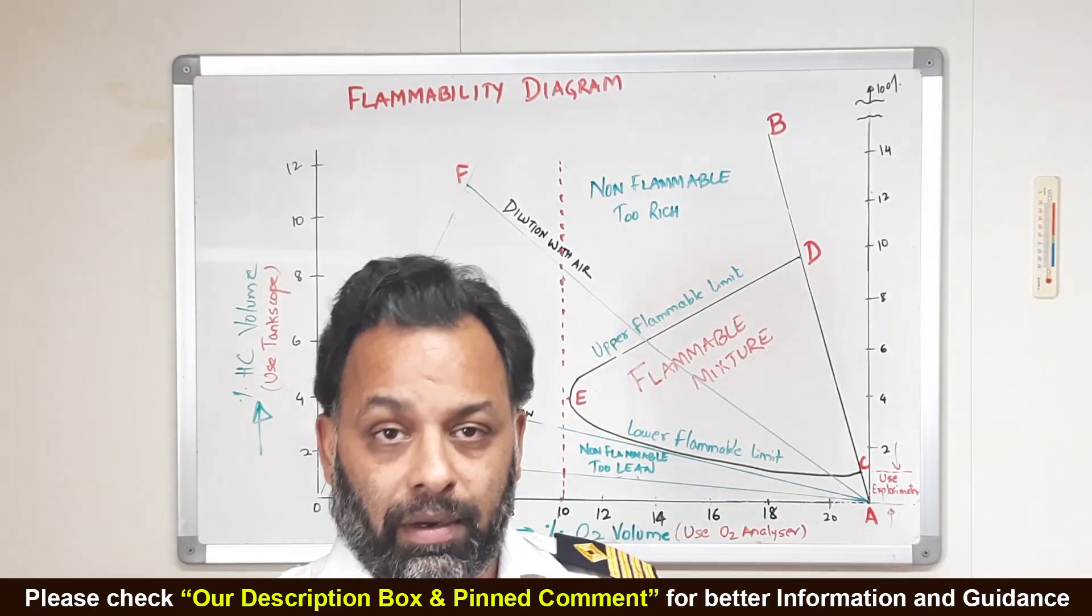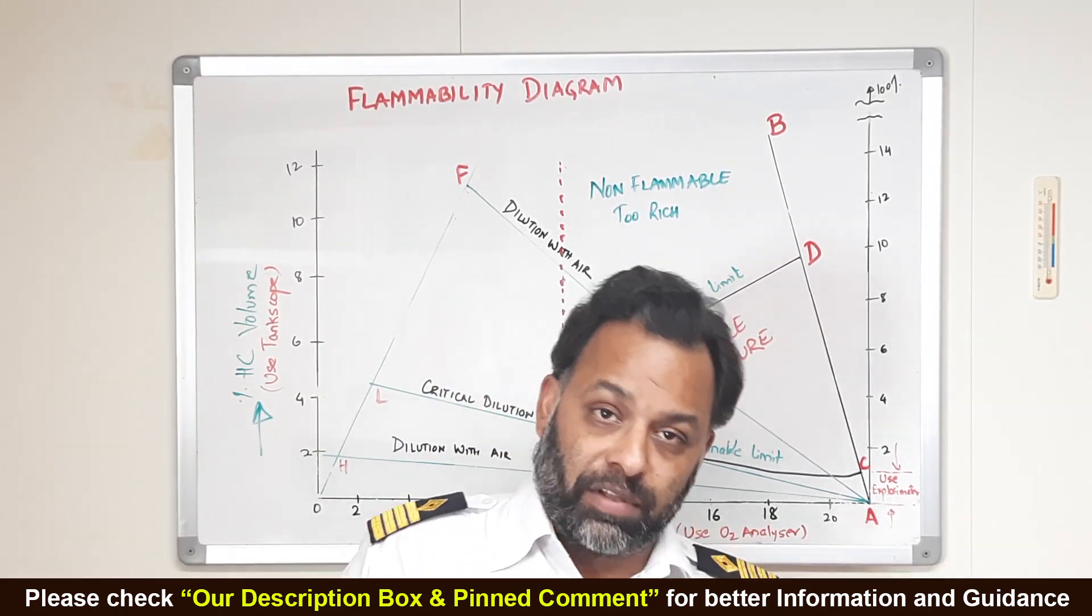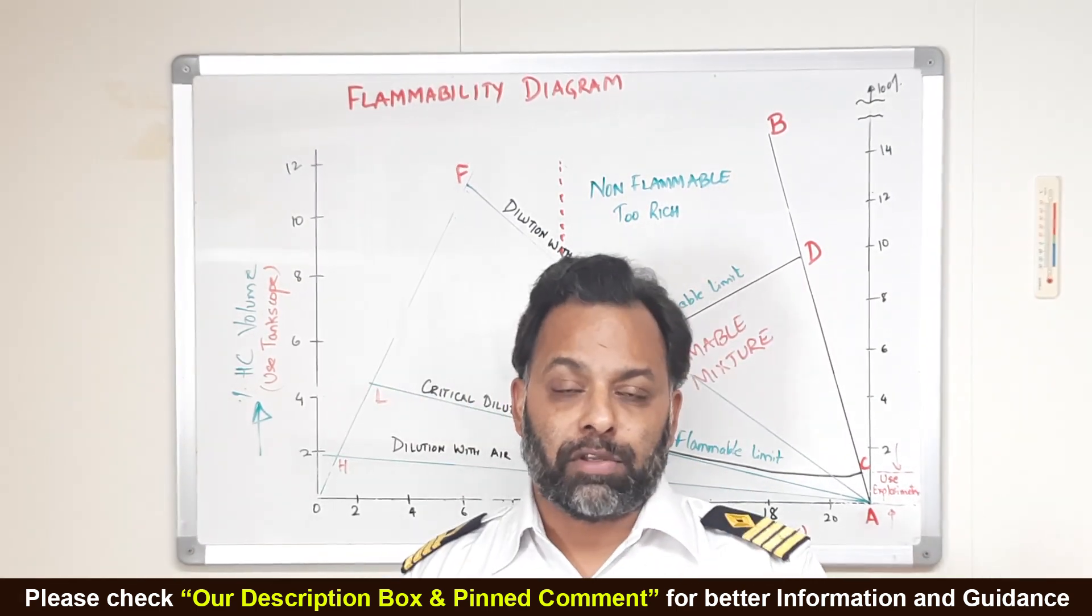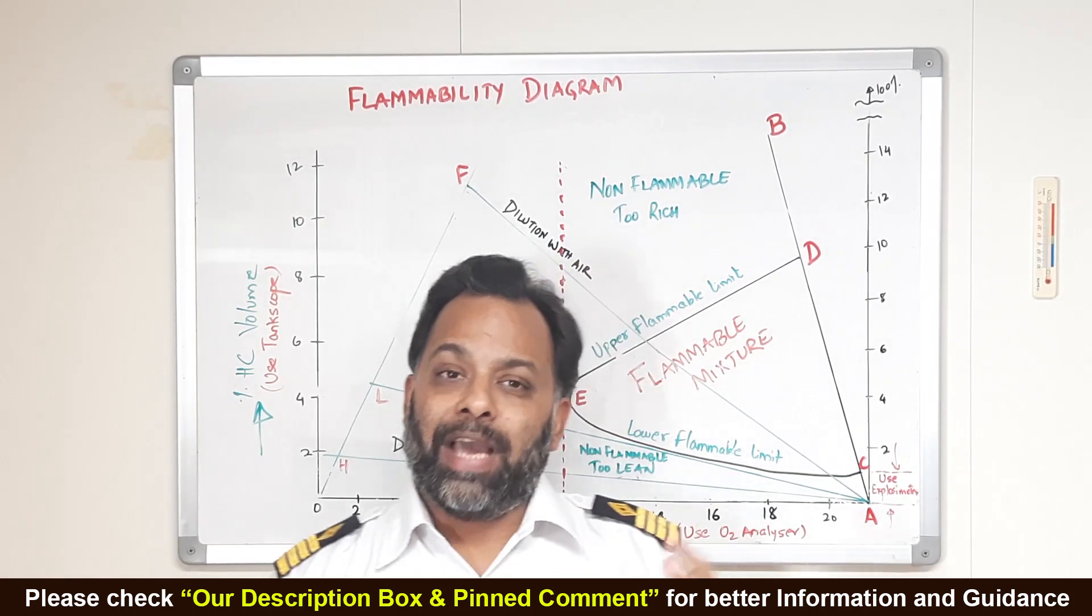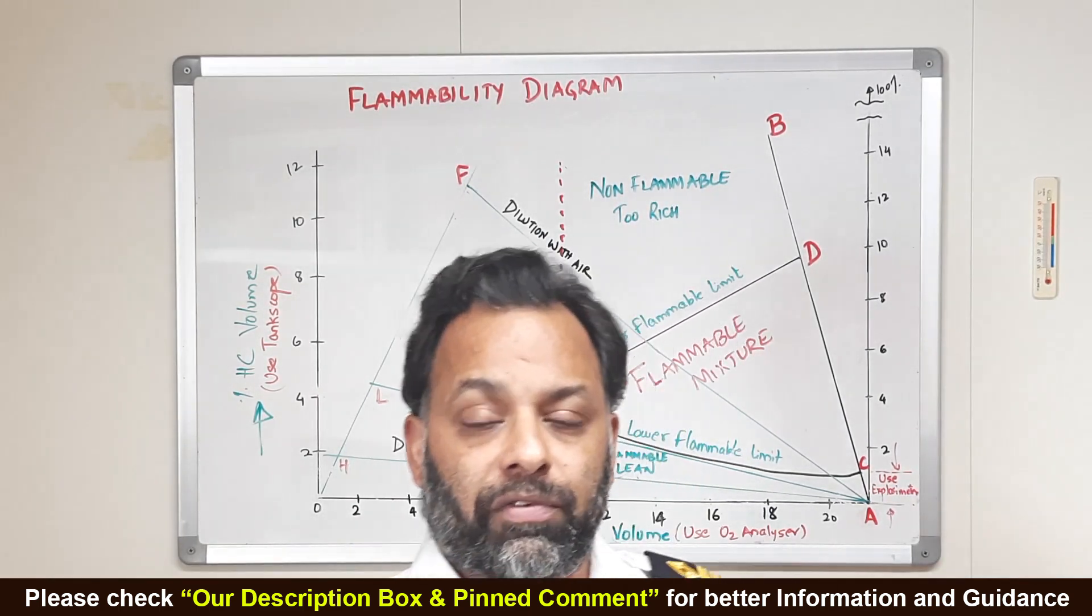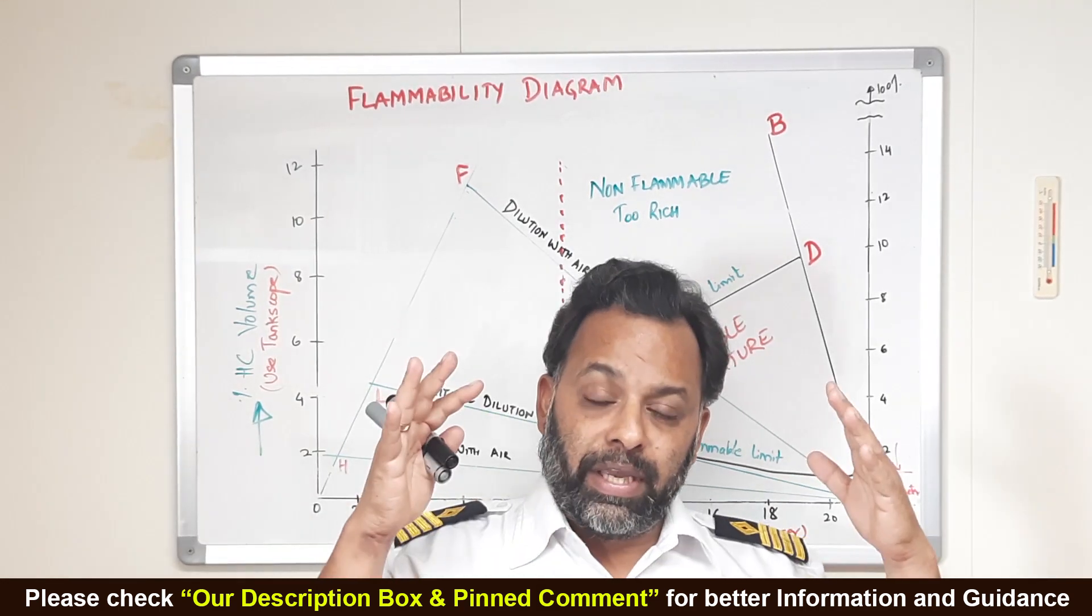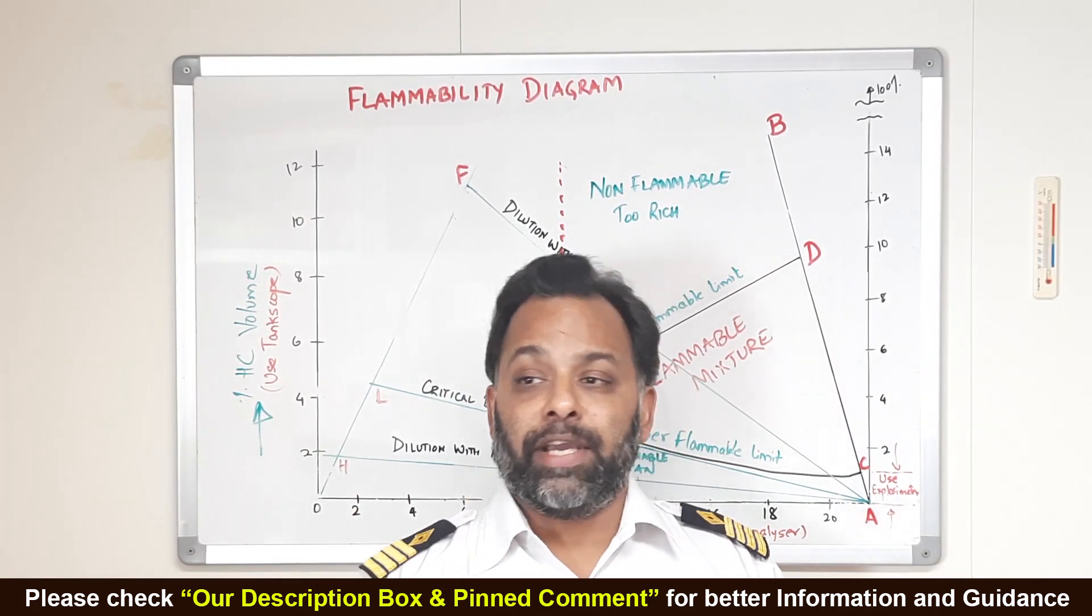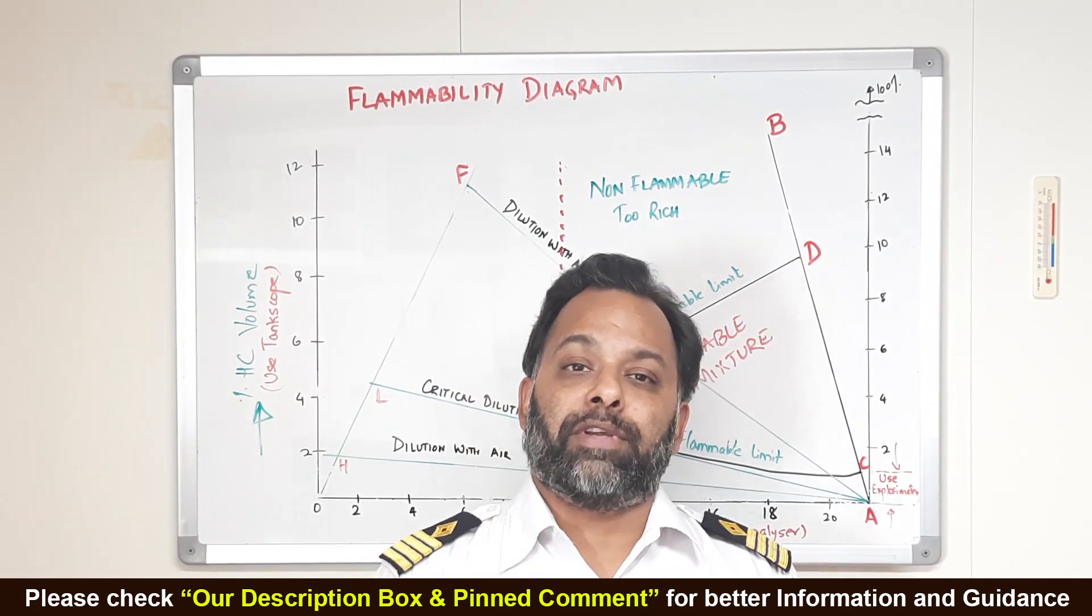Third thing is air. We can definitely take away air from the system, from the tanks by introducing something which is called inert gas. We have inert gas generators, inert gas systems through which we put that inert gas into the atmosphere, which contains less than 5% of oxygen. And hence we take away one element of this fire triangle.